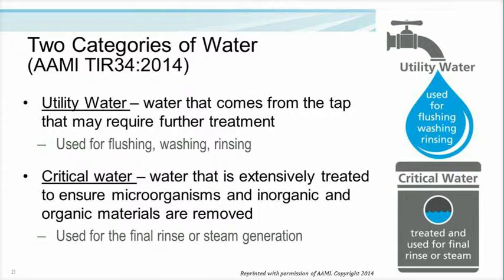The 2 categories of water that the committee defined are utility water, which is water that comes from the tap that may or may not require further treatment. This type of water is used for flushing, washing, and rinsing steps in reprocessing. The second category is considered critical water, which is water that is extensively treated to ensure microorganisms, inorganic and organic materials are removed. This type of water is used for the final rinse in disinfection or steam generation.